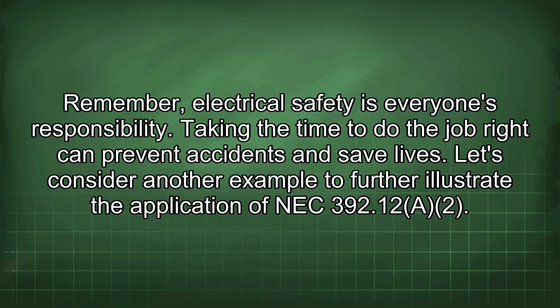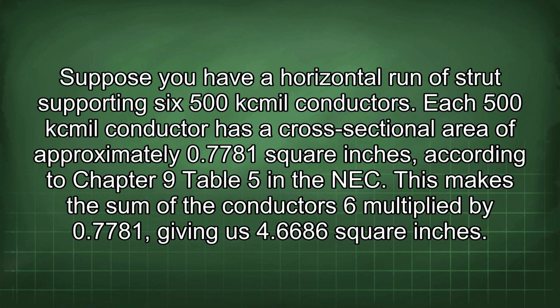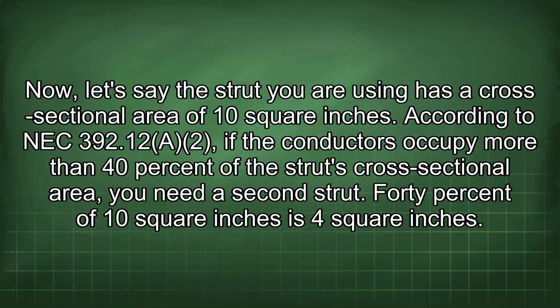Let's consider another example to further illustrate the application of NEC 392.12. Suppose you have a horizontal run of strut supporting 6 500 kcmil conductors. Each 500 kcmil conductor has a cross-sectional area of approximately 0.7781 square inches according to Chapter 9, Table 5 in the NEC. This makes the sum of the conductors 6 multiplied by 0.7781, giving us 4.6686 square inches. Now, let's say the strut you are using has a cross-sectional area of 10 square inches.